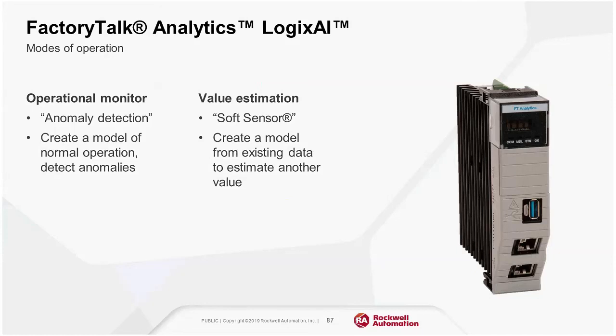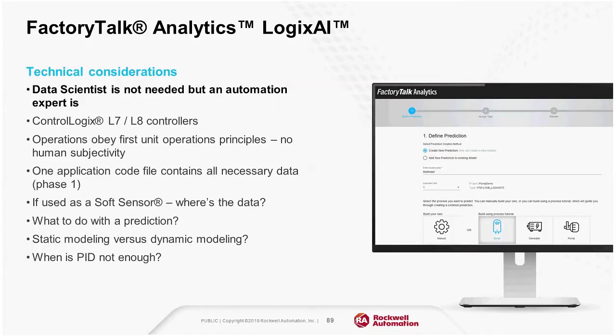There are essentially two modes of operation for Logix AI: anomaly detection and soft sensing. Anomaly detection is when Logix AI creates a model of normal operation and then tries to detect anomalies — for example, the module can help operators spot performance deviations in equipment like mixers that could affect product quality or lead to downtime. Soft sensing is when Logix AI creates a model using existing data to estimate another value — for example, predicting the humidity of a packaged food product by analyzing variables from line assets like sprayers, dryers, and burners, rather than an operator taking a manual reading.